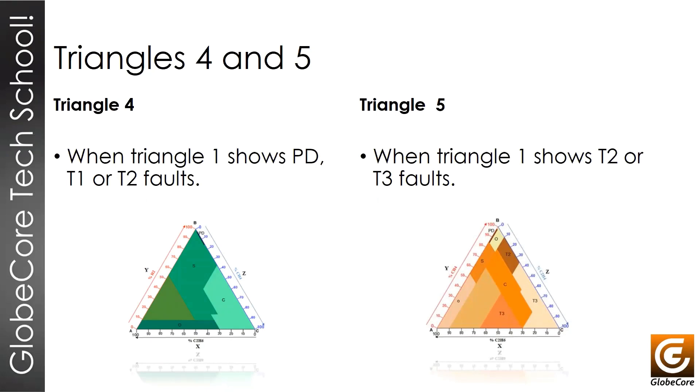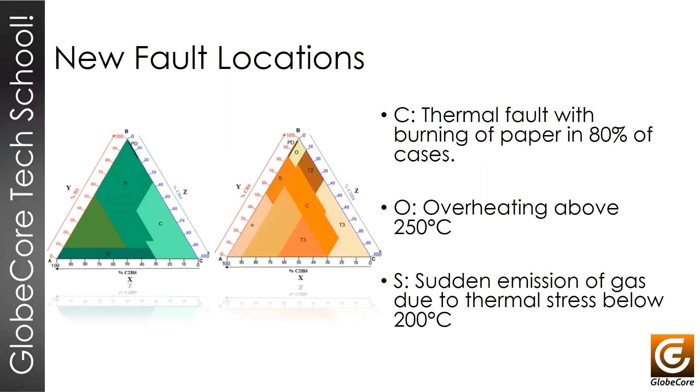The T4 triangle is used for a more in-depth study of faults related to partial discharges, T1 or T2 faults. T5, the fifth triangle, is used in case of high energy faults, T2 or T3. The T4 and T5 are not used in cases when the problems are purely electrical. These triangles additionally define three new fault types: a type C fault, and types O and S. A C-type fault is a thermic fault that is accompanied by paper carbonizing in 80% of cases. An O-type fault is an overheating with temperatures over 250 degrees centigrade. The S-type fault is unexpected gassing in mineral oil that happens due to thermal stress and usually due to poor oil refining.